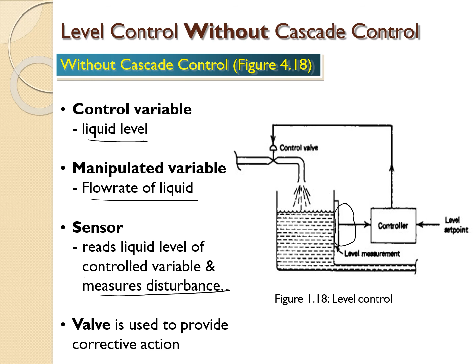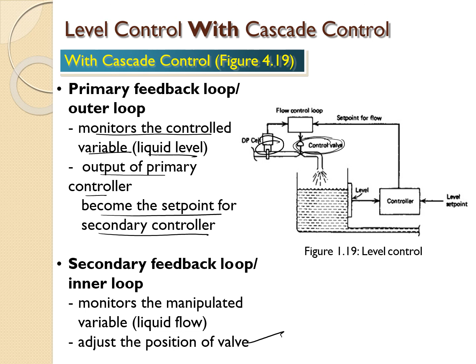Okay, level control with cascade control. The primary feedback loop, or outer loop, is used to monitor the control variable, which is our liquid level. This one is our control objective. The output of the primary controller becomes the set point for the secondary controller. The secondary feedback loop, or inner loop, monitors the manipulated variable, which is our liquid flow here, and adjusts the position of the valve. So here is the manipulated variable. It is monitored here and then the adjustment is made at the position of the valve.